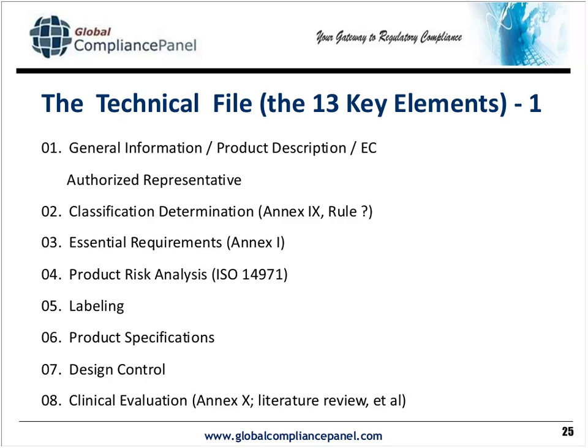You can include that data in your technical file in lieu of actually running clinicals. And the FDA is looking at that more and more. You'll notice that the new 510K allows for submission of literature regarding clinicals. And if it's sufficient and detailed enough and addresses specific issues of your product, they will accept that in lieu of clinicals.